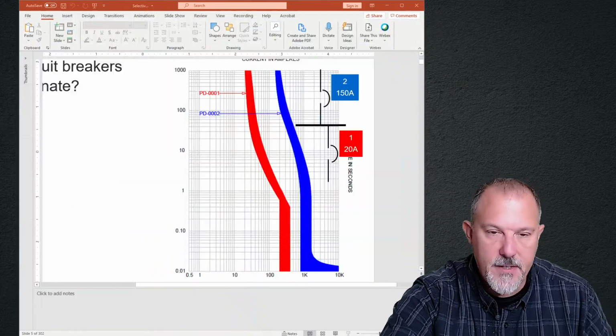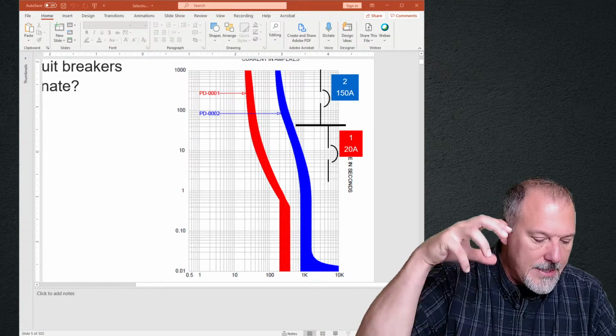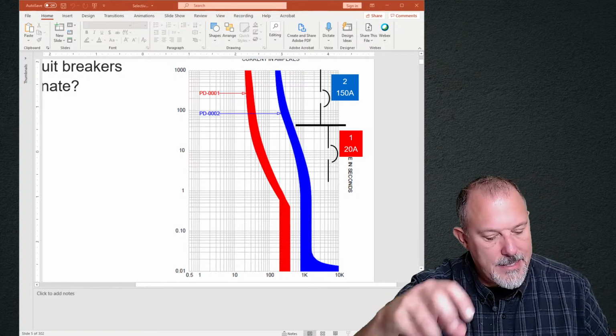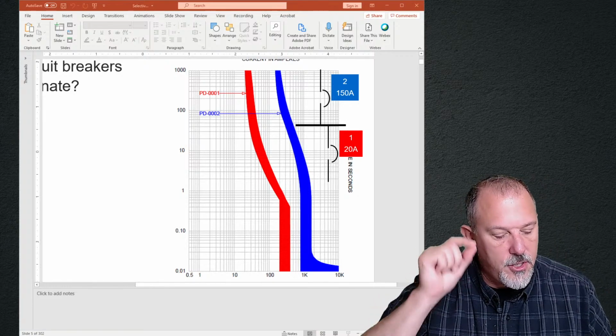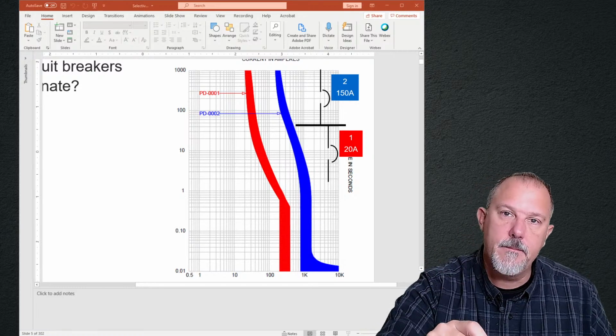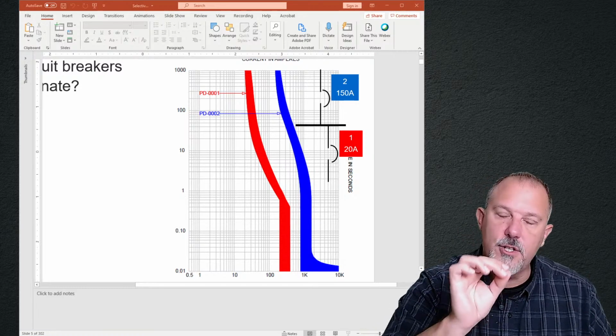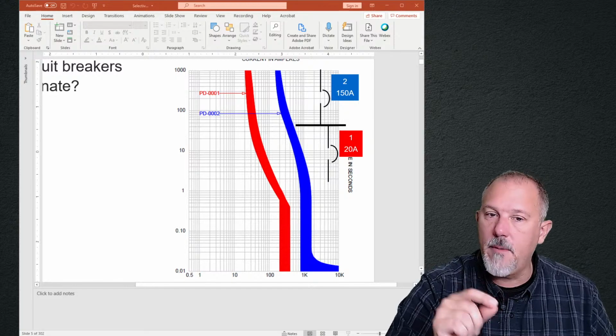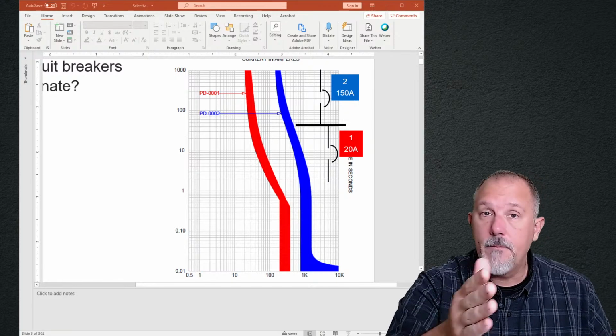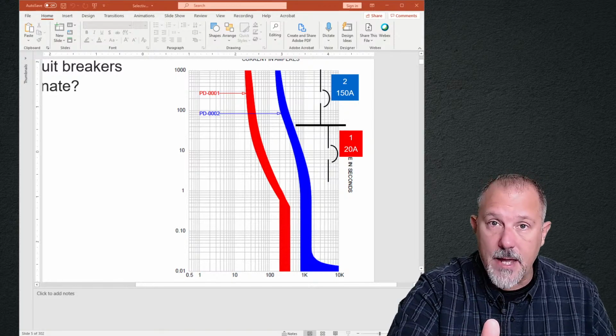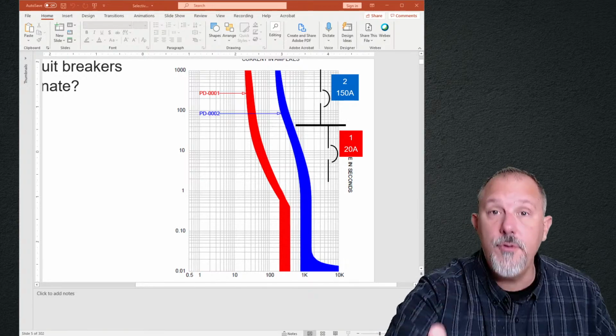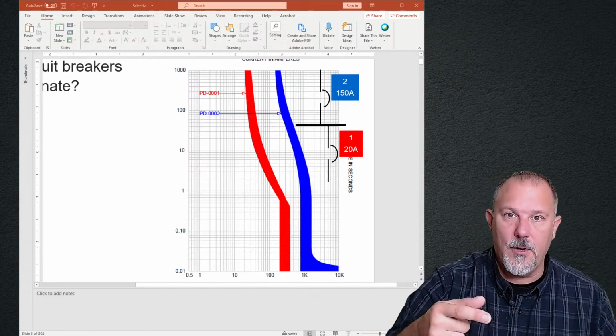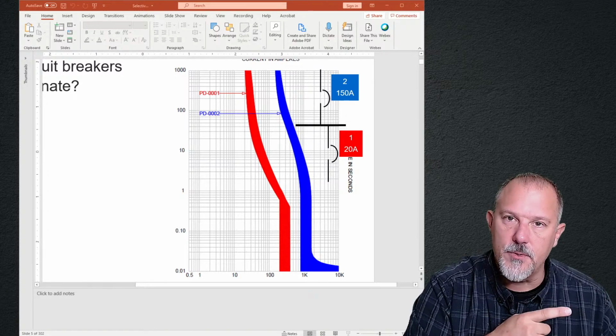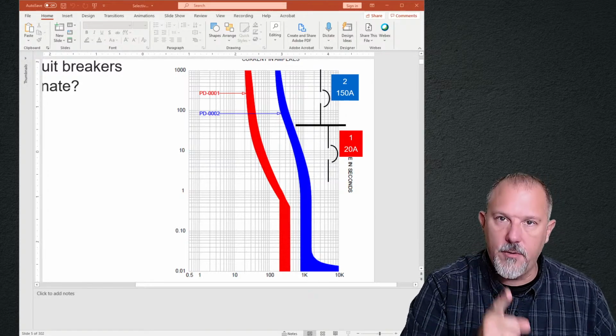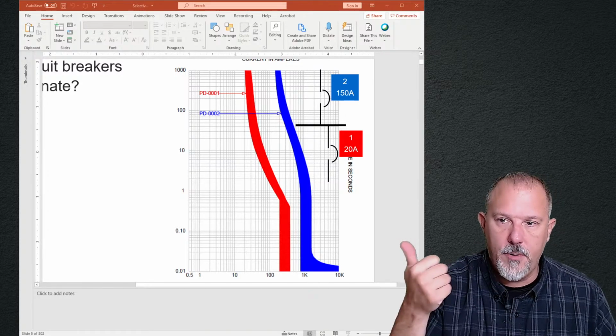And what does the definition say? The definition says localization of an overcurrent condition to restrict outages to the circuit or equipment affected. I can stop right there. If I know my fault current is 10,000 amps, or if I know my fault current is 5,000 amps, or if it is 2,000 amps, I know based upon those tables that anything greater than 1,500 amps, both of those are going to open.